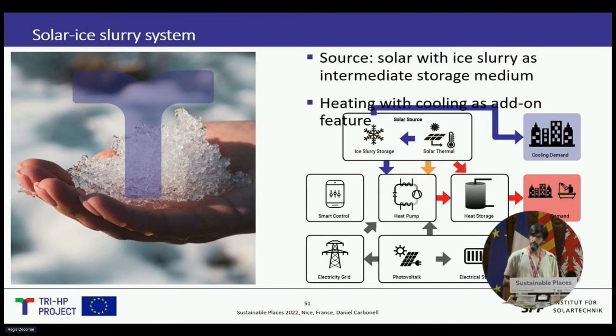This system uses solar thermal collectors as a source for the heat pump, but since we don't have enough solar resources in winter, during foggy weeks, or at night, we use a water storage as a source for the heat pump, regenerated by solar with high efficiency. The heat pump can extract enough energy to convert the water into ice. This kind of system exists in Switzerland and Central Europe, but our innovation was an ice storage that is much cheaper, using an ice slurry concept, which lets us eliminate the heat exchangers in the ice storage entirely. This system also features an advanced energy management system with model predictive control.